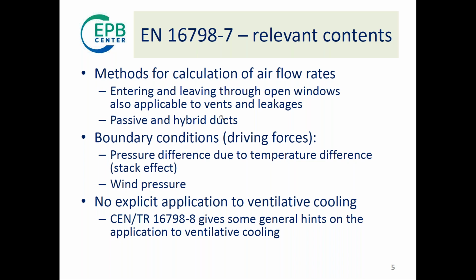Also included are airflow rates for passive and hybrid ducts, which involves a bit more technical detail. These calculation methods consider boundary conditions as driving forces, such as pressure difference due to temperature difference, the so-called stack effect, but also wind pressure.